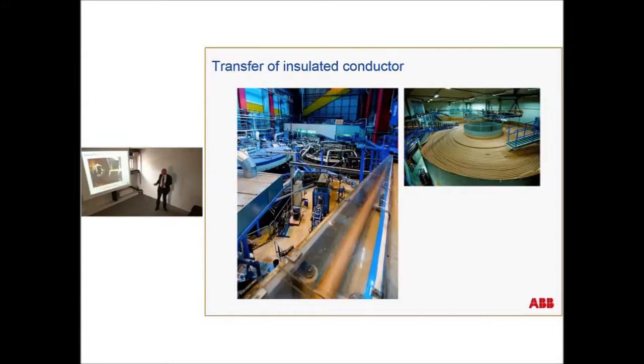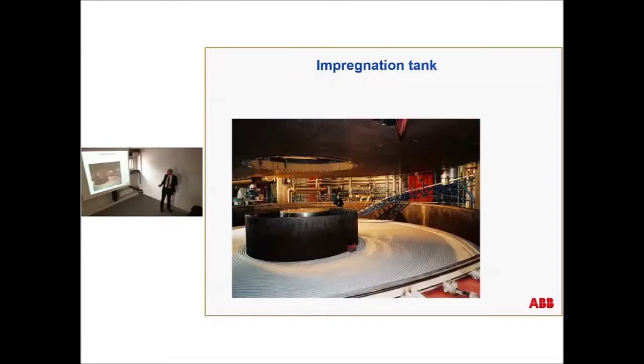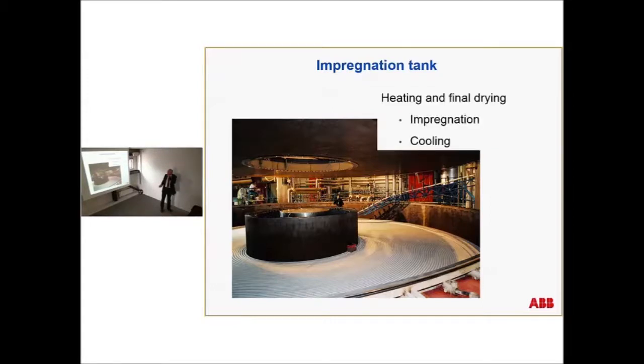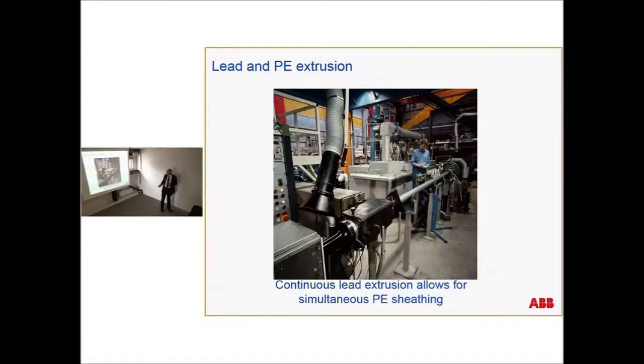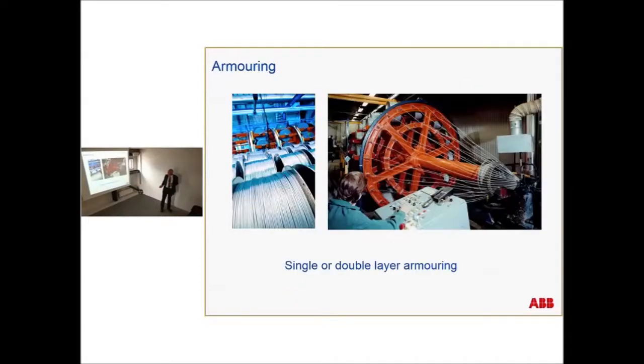You transfer that into a large coil or something, where you then impregnate the cable. That must be done under controlled humidity and temperature, as for all other paper and oil insulated products like transformers. We have an impregnation tank here where you impregnate the paper. Then you cool it down. Then it's ready for the lead extrusion. And finally, you do the armoring, single or double layer, depending on the mechanical requirements on the cable.